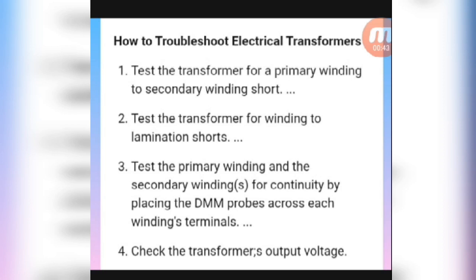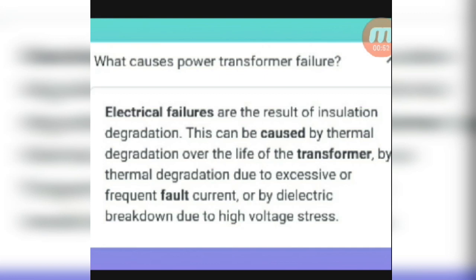Check the transformer output voltage. Electrical failures are the result of insulation degradation. This can be caused by thermal degradation over the life of a transformer, thermal degradation due to frequent fault current, or by dielectric breakdown due to high voltage stress.